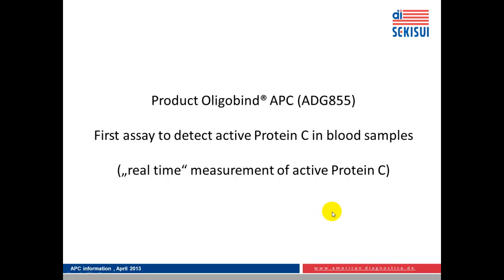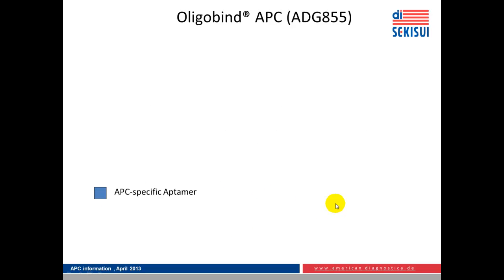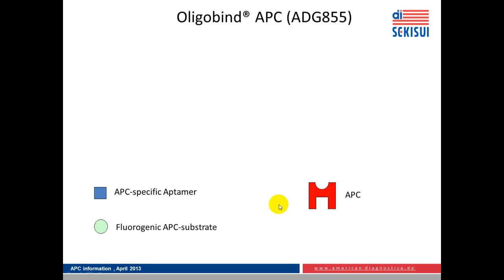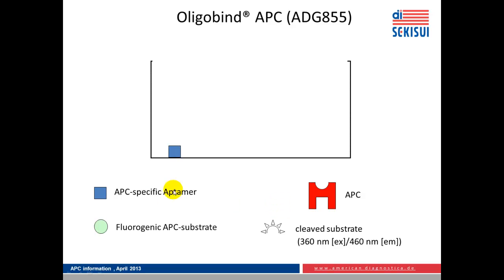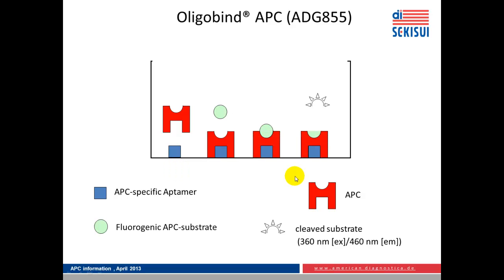It allows real-time measurement of active protein C. Here is a schematic overview on the setup of the assay. It's based on APC-specific aptamers which bind activated protein C in a specific manner. There is a fluorogenic APC substrate that allows quantification of the functional activity and the cleaved substrate. This APC-specific aptamer is bound to a solid phase — a 96-well microtiter format. APC in the sample is captured, then a fluorogenic APC substrate is added and converted to a fluorescent product that is measured in a fluorometer.